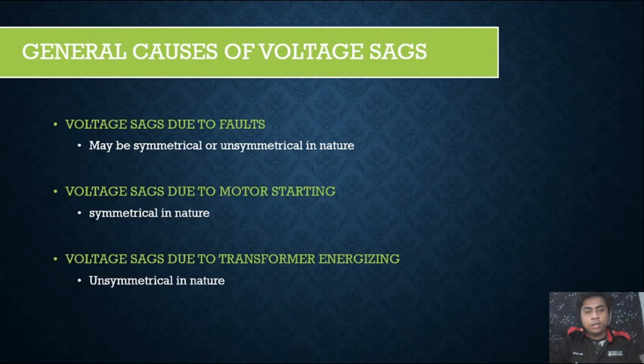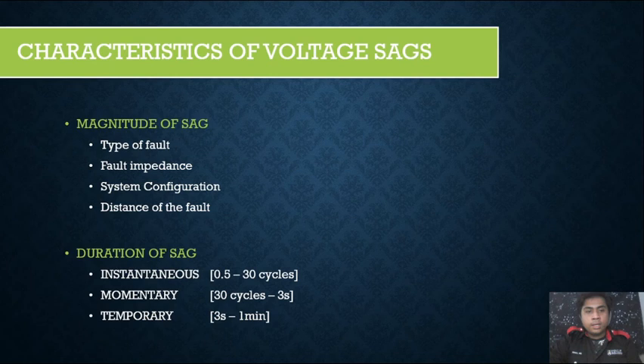So, there are several characteristics of a voltage sag in a power system: magnitude of sag, type of fault, fault impedance, system configuration and distance of the fault. Regarding the type of fault, voltage sags can be classified as balanced and unbalanced depending on the type of the faults. There are 7 basic voltage sag types according to ABC classification, from type A to type G. The duration of the sag can be instantaneous, 0.5 to 30 cycles, momentary, 30 cycles to 3 seconds, and temporary, 3 seconds to 1 minute.